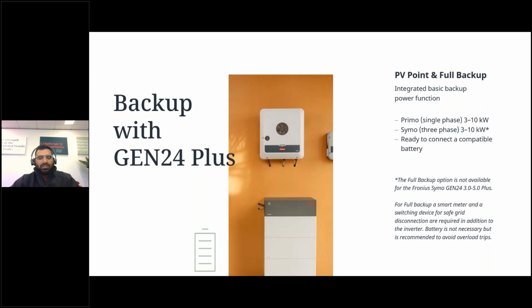All right, let's move on to the backup capabilities of GEN24 Plus inverters. With GEN24 Plus, we can do both PV Point and full backup. PV Point is exactly the same as on GEN24 inverters, so I'm not going to talk much about it. Let's move on to how to do full backup on the GEN24 Plus inverters. With regards to full backup on the single phase Primo range, we have full backup possible from 3 to 10 kilowatt inverters. But on the 3-phase ranges, we do not have full backup available on 3 to 5 kilowatts. So it is only possible to do full backup from 6 to 10 kilowatt on the SYMO range. That is one of the important topics to consider.